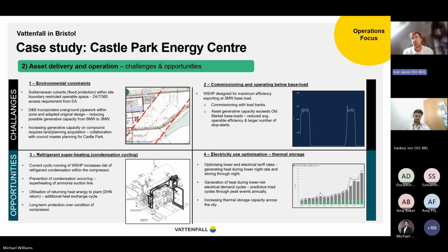And finally, the opportunity we have around electrical use optimization. So we are planning to maximize our electrical tariffs and local thermal storage, essentially, to be able to charge the local body of water to the greatest depth and amount that we can, and obviously run off of that during those peak hours. But that does require a larger thermal storage capacity across the city, and is something that we've identified within the business that we would very much look at doing for all of our future assets, especially as we move towards more of a heat pump focus. So if you want the next slide, please.